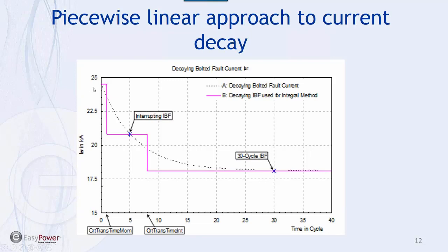If they are still connected, then I have a memory, and I know how much current they used to see and how close they have got to their final trip time. We have a mechanism to keep track of that, because it's a protective device. It works based on the current, and as long as the current hasn't dropped below the pickup value, it still is counting.